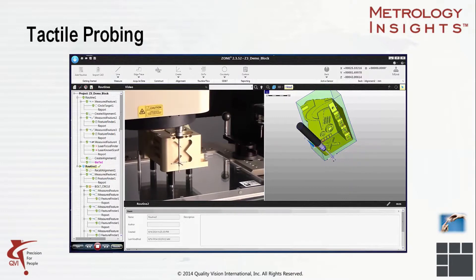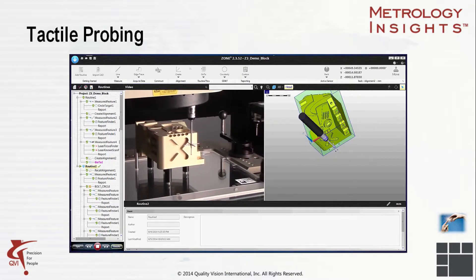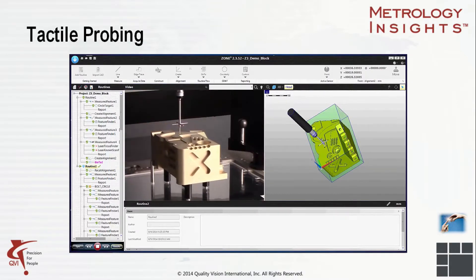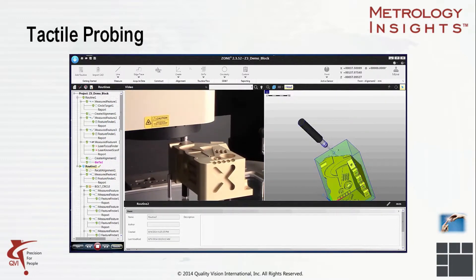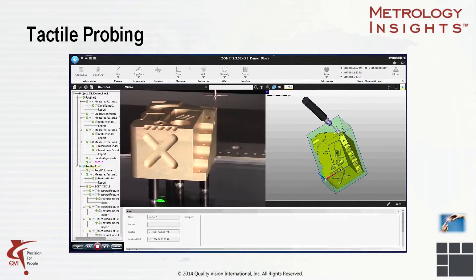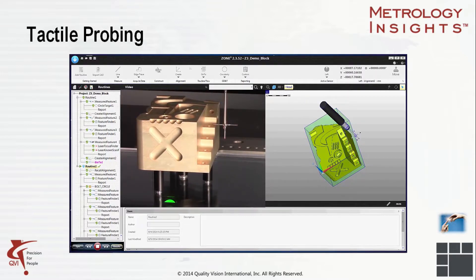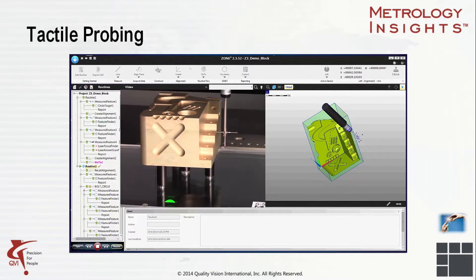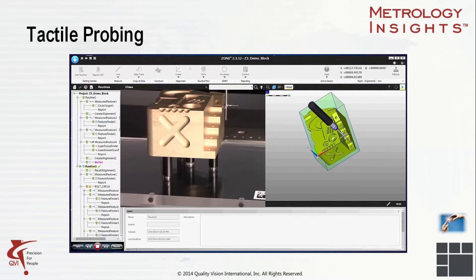Some kinds of measurements simply can't be done using visual methods alone. For example, using optics alone, the side of the part cannot be measured. To measure down the outside or an internal feature, a touch probe is needed to reach in and measure where the optics can't see. This particular example uses a CAD model to program the part. We have identified the clearance zone around the part so the machine can easily maneuver the touch probe around the part without crashing. With the clearance zone in place, we can proceed to measure by acquiring points at various locations on the part and constructing them into desired features.